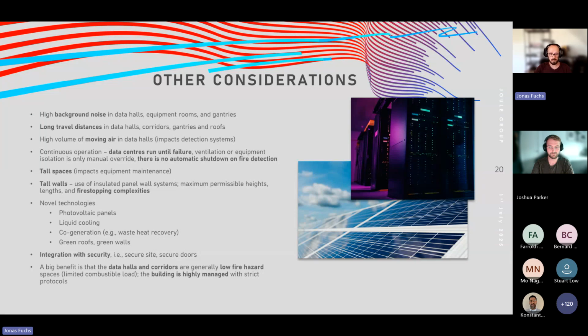Data centers require continuous operation. So if you have an incident in the data center, it's typical that there is no power isolation. They continue to run until either the incident is taken care of or until a big red button has been pushed somewhere because somebody has the authority to say so, or until the data center has failed. So it's something that needs to be considered. There is no automatic shutdown on fire detection, as you may see in other buildings.